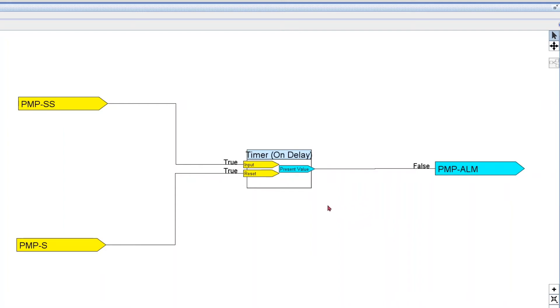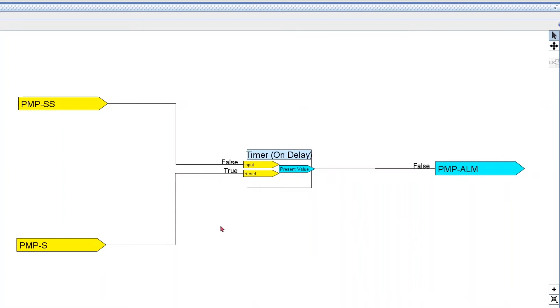This is the most basic example. But let's say that my controller wants to stop the pump but the pump is still running. With this logic, it's not gonna work. The scenario is: the controller is telling the pump to stop and somebody turns on the pump manually, or there's a problem with the feedback — so you're not gonna get an alarm. I usually don't need an alarm when status is on and there's no command, but if you do, I'll show you how in the next example.